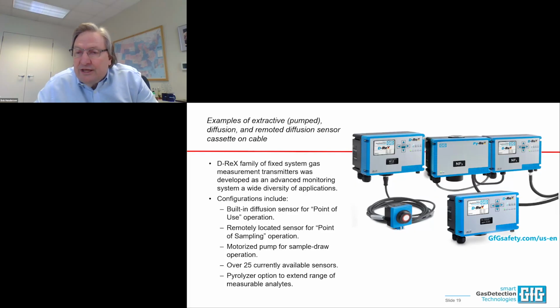Another method of getting the gas into the sensor is to take the sensor cassette out of the unit and put it out on the end of an extender cable. So now you have a local display, push button controls, but the sensor itself might be in an awkward place that you can't easily get at and would not be able to see the readings. So that's another way you can go.